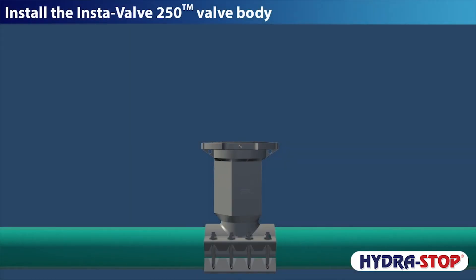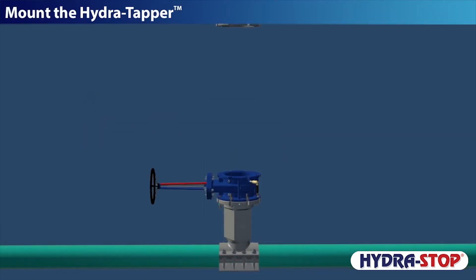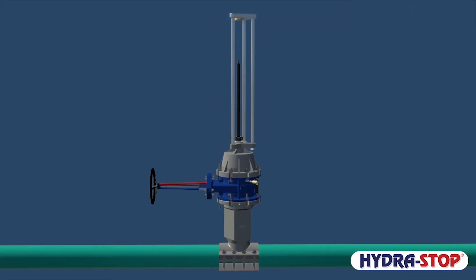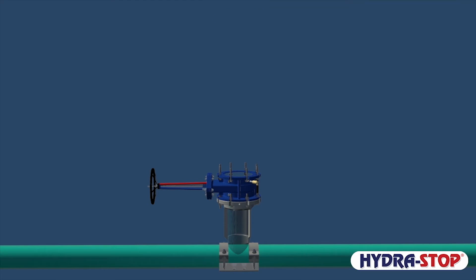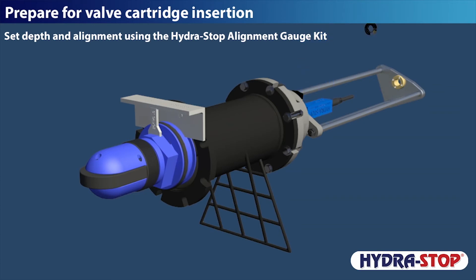To install the InstaValve 250: first, install the InstaValve 250 valve body; then mount the temporary gate valve; mount the HydraTapper; and make the line tap. Tried-and-true line tap methods are used, and coupon retention is utilized for inspection, evaluation, and verification purposes. Then prepare for valve cartridge insertion by setting depth and alignment using the Hydra-Stop alignment gauge kit.